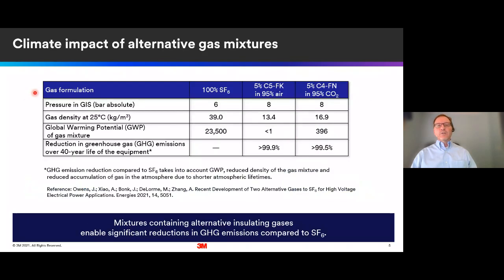So what's the impact of using those kind of gas mixtures then in gas insulated equipment? Well, this table shows an example of some of the kinds of gases that are used in the equipment Renee described. Matter of fact, I think Renee has seen this kind of mixtures come through the KEMA Labs for testing and qualification. In the case of the fluoroketone-based gas mixture, regardless of what the concentration or mix ratio is, you're able to achieve really the intended goal of using an SF6 alternative, which is essentially eliminating greenhouse gas emissions from the application.